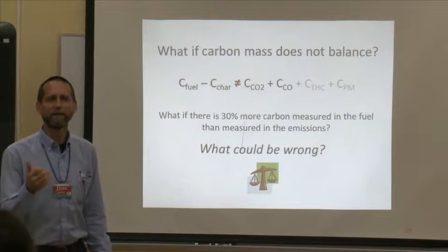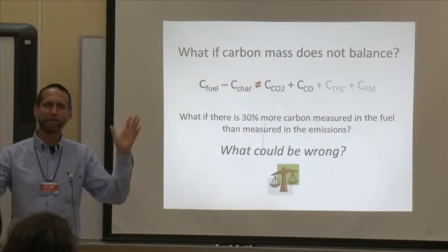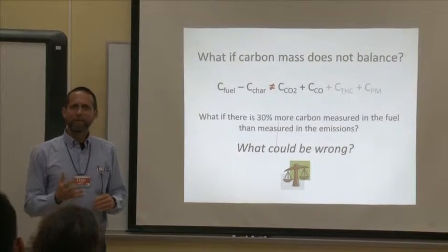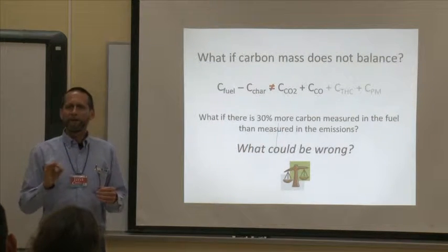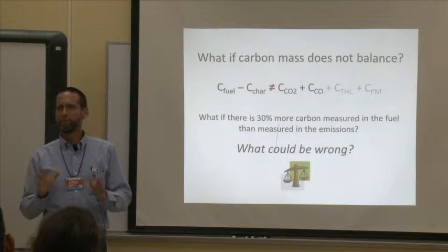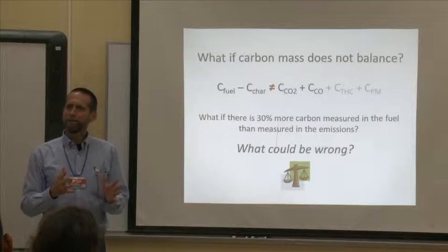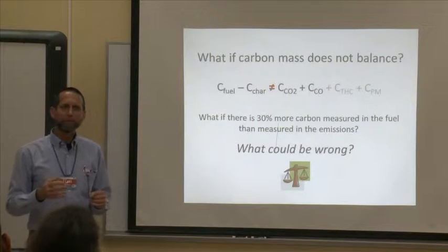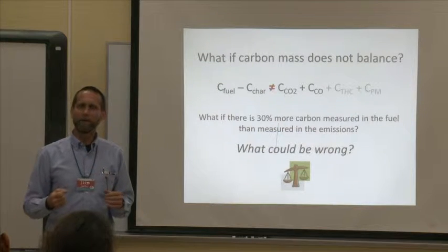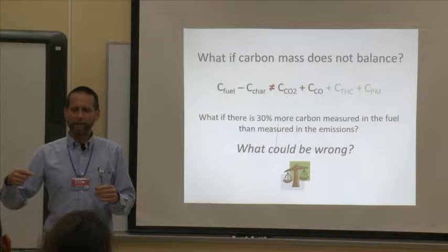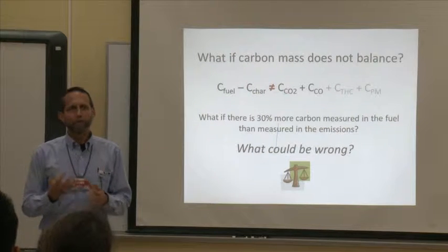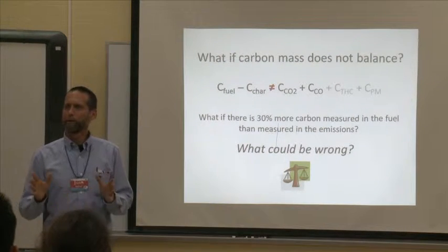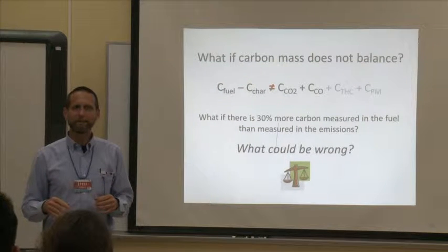Okay, emissions, that is the first thing we thought of too. If emissions are escaping from the hood, then that could cause that problem. We couldn't see any emissions escaping from the hood, but we could smell a little bit of emissions in our lab. So we thought, maybe we're losing something. In tracking down where that smell was coming from, we found one of our instruments had a vent on it that wasn't properly vented to outside. We thought we had solved the problem. We fixed that. That's not what it was.